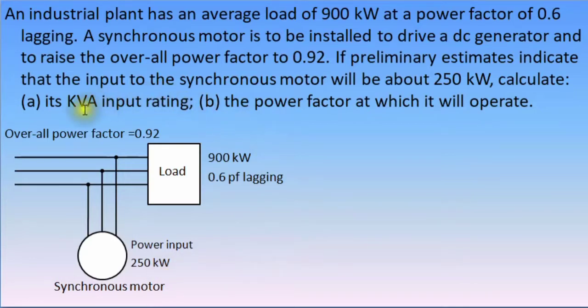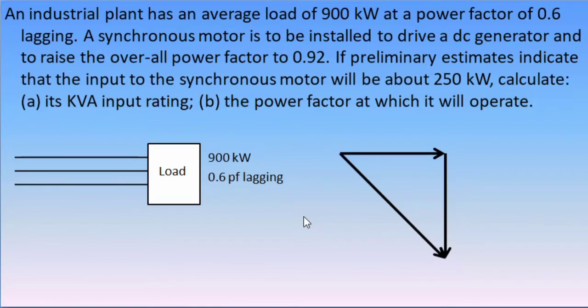Anyway, we are asked to determine the KVA input rating of this synchronous motor and the power factor at which it will operate. We will be solving this problem using Phasor diagrams. First, let's take a look at the original Phasor diagram when the synchronous motor is not yet installed. The effective power consumed by the load is 900 kilowatts.